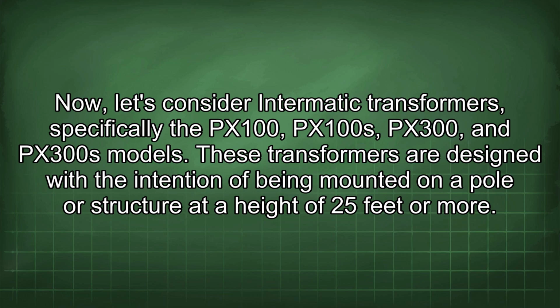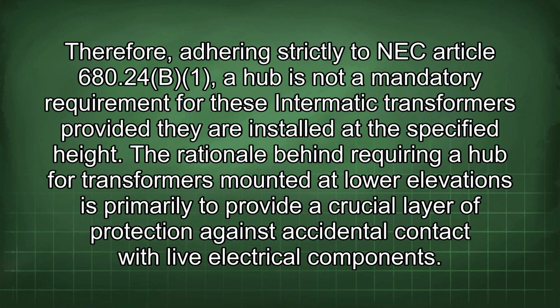These transformers are designed with the intention of being mounted on a pole or structure at a height of 25 feet or more. Therefore, adhering strictly to NEC Article 680.24(B)(1), a hub is not a mandatory requirement for these Intermatic transformers provided they are installed at the specified height.